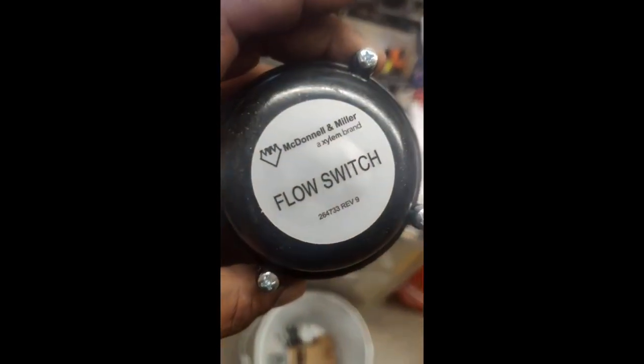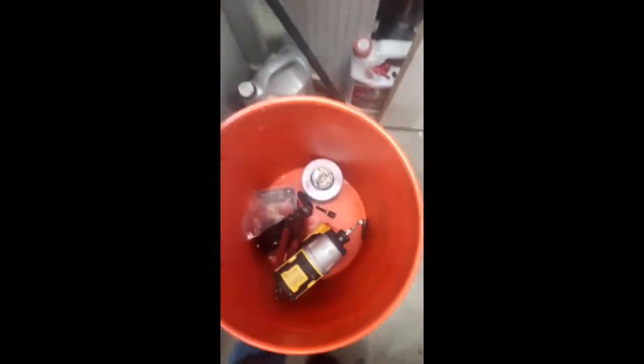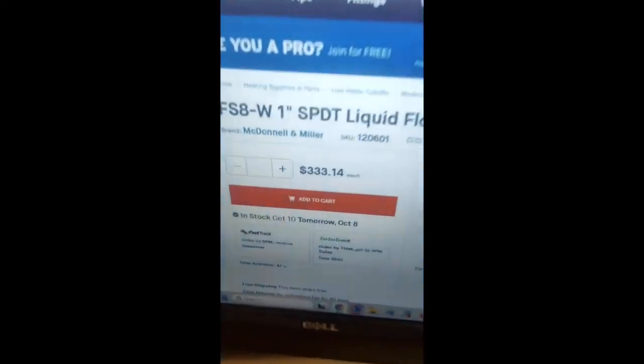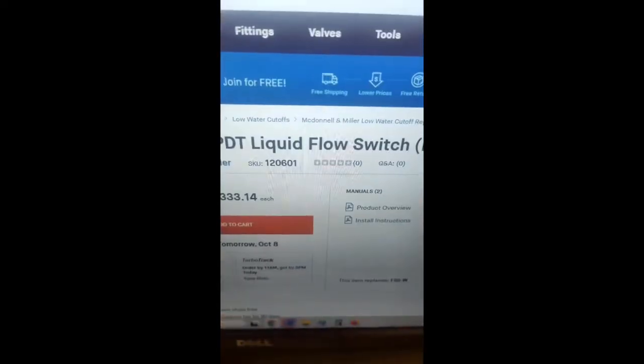Okay, so we got this flow switch for ER252 Lochinvar pool boiler. This is a water boiler. We're not heating air, we're heating water here. This is the flow switch right here. Liquid flow switch. I think it closes at around 5 psi, something like that. It doesn't have a high low limit on it.